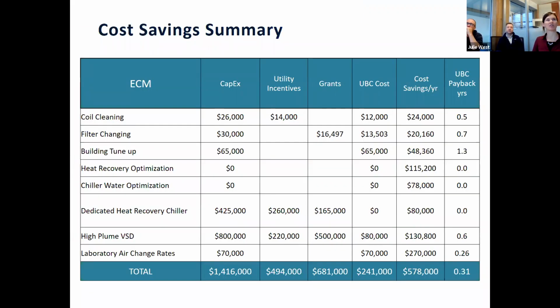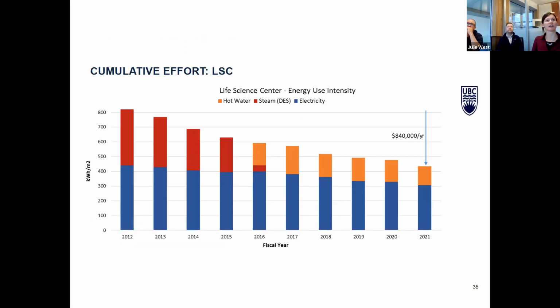So in summary, this is all of the energy savings projects that we've done in this building to date. There's actually an additional one: we added some drives last year that I didn't have time to put on here because we haven't M&Ved it yet. But you can see the CapEx for all of these projects is roughly 1.5 million. We received around $500,000 in utility incentives, $681,000 in grants. UBC's cost was only $240,000, but we've seen roughly $600,000 per year in cost savings. So our payback was less than 1 year. And that's how we got from 800 kilowatt hours per square meter to roughly 400.